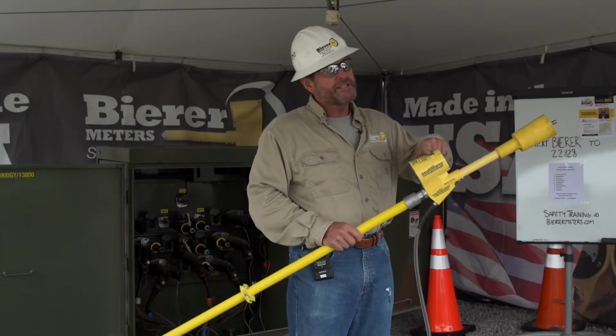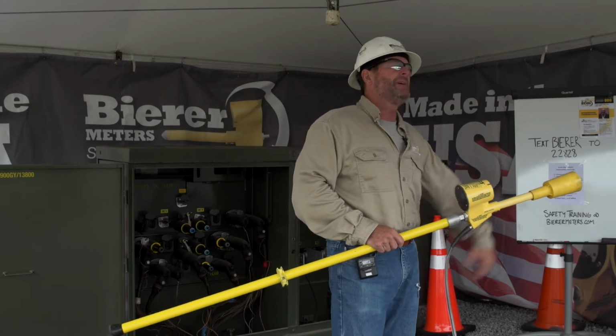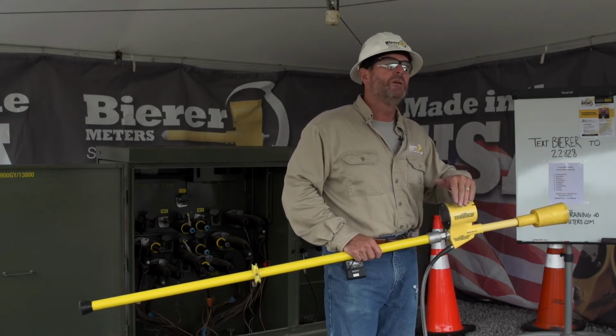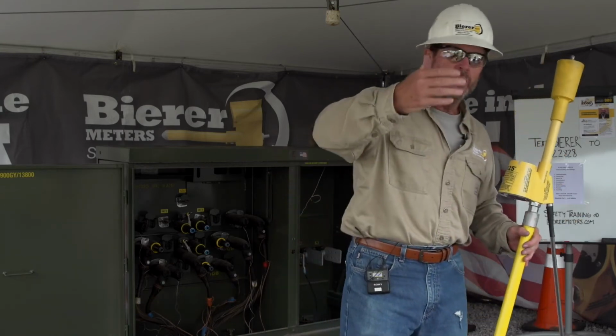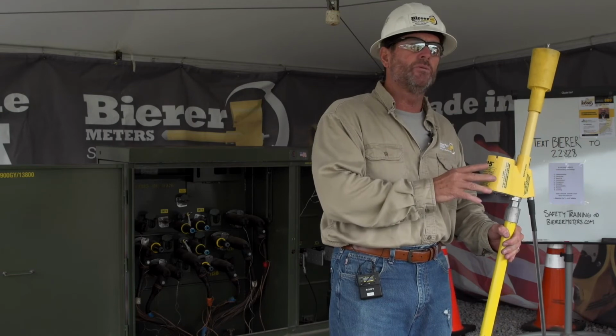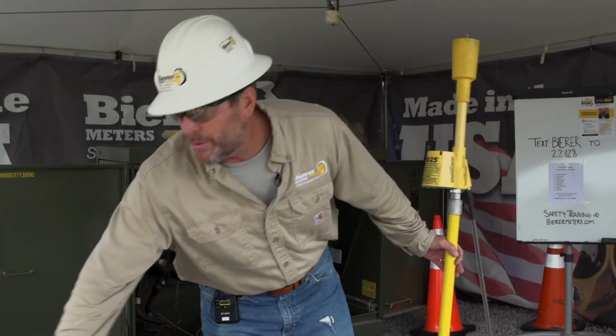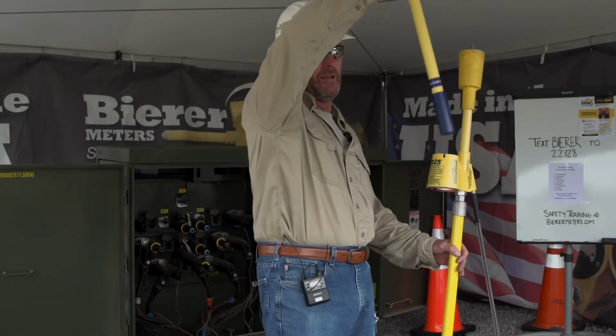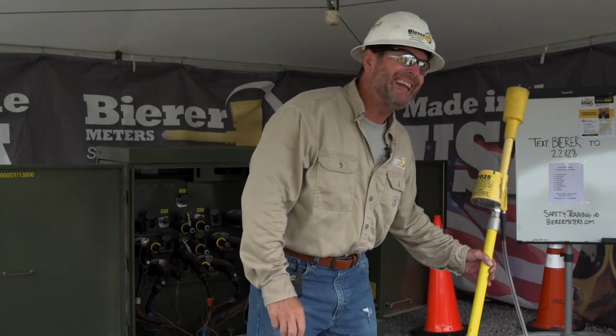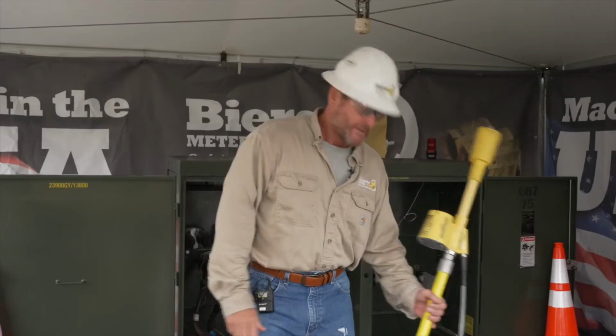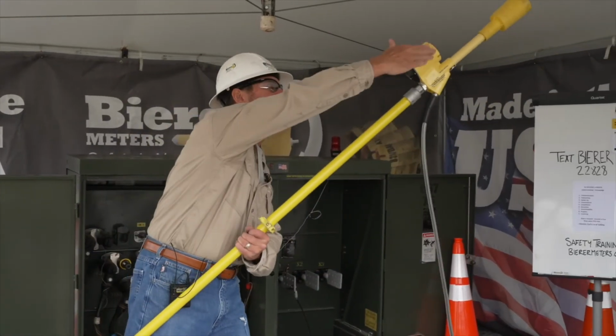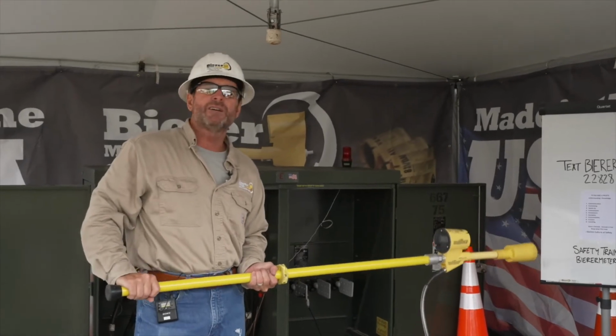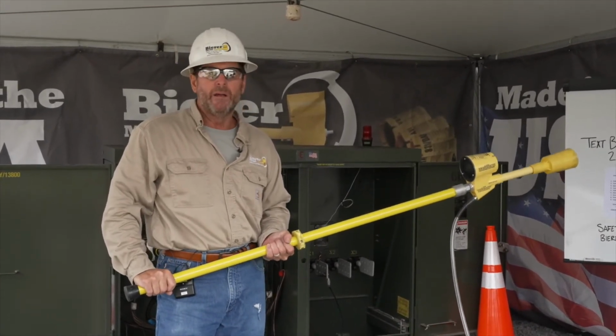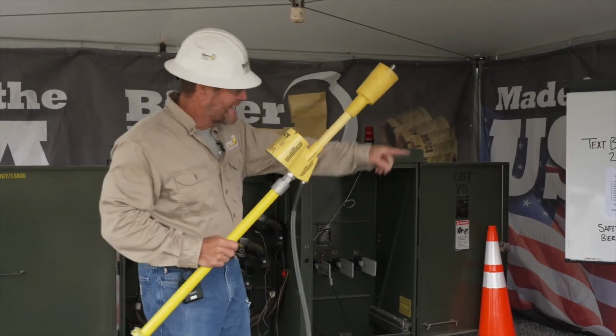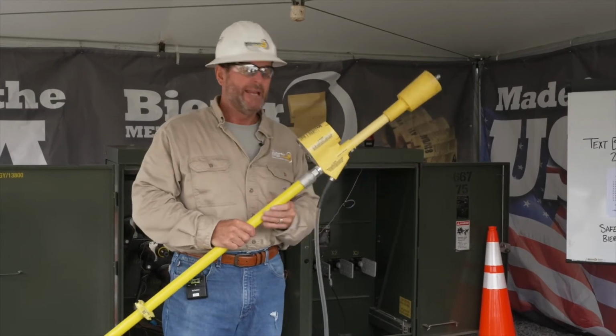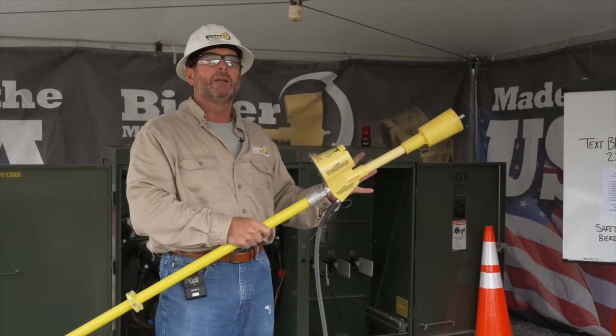Going to ground—this meter head, in this particular utility, was next to another hot phase. So instead of inspecting their work area prior to using the tool and knowing how these tools function, they should have put on a zero ohm extension prior to use. But they didn't, because they needed the lineman safety and tool training, so they didn't know. So when they made contact, and that hot bus was right next to the meter head, they had a cross phase arc flash. That potential shot down that cord to the secondary probe and blew up at the housing.